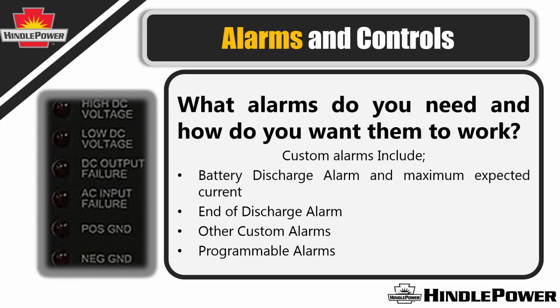The other is an end of discharge alarm. Now, end of discharge alarms are basically kind of low voltage alarms. They let you know when the batteries reach the end of discharge. And for lead acid batteries, and particularly valve regulated and even wet lead, knowing the end of discharge is important because you may want to disconnect the battery from load when you reach a certain voltage, because if it goes beyond that voltage going down, you could start to cause damage to the battery like sulfation and other things.